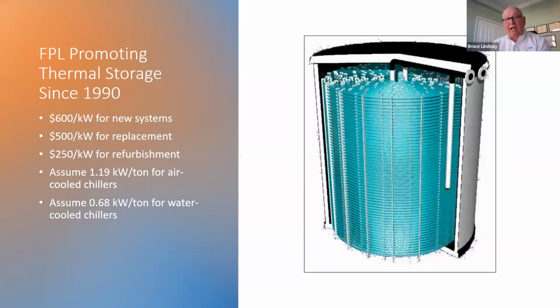For those of you who aren't familiar with ice storage, here is your round tank. They have round tanks and they have rectangular tanks. The round tanks are made of plastic. The rectangular tanks are made of steel. These tanks, as you can see, are heavily insulated using a styrofoam on top, on bottom, all around it. Very little energy loss. Very efficient, good round trip efficiency. Inside the plastic tubing, there's 3 miles of plastic tubing circulating a water glycol mixture. It freezes the ice, and we reverse the process to cool the building. Next slide.